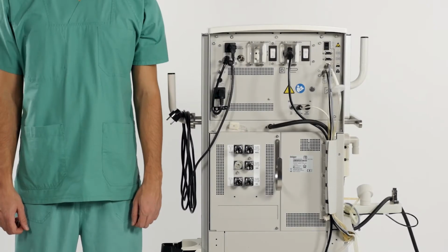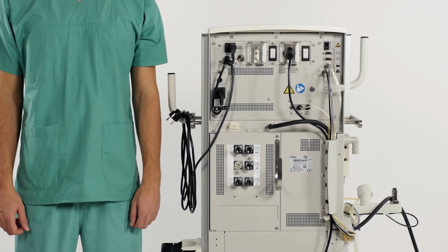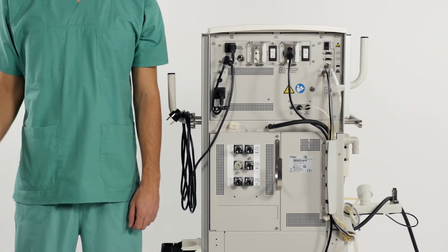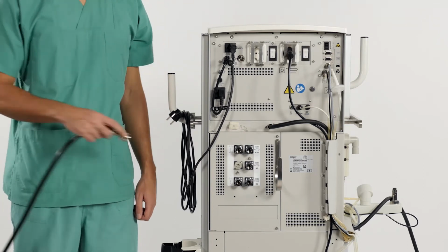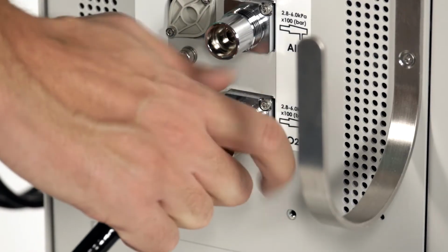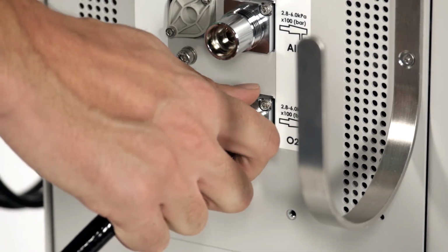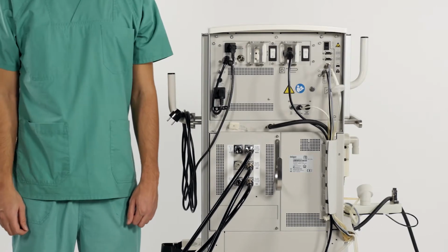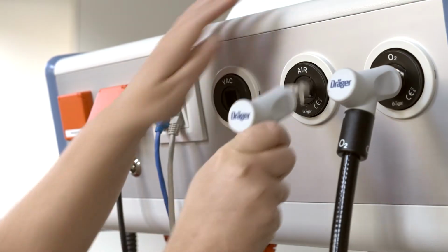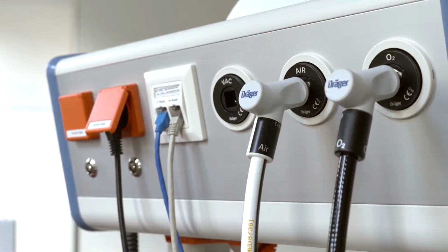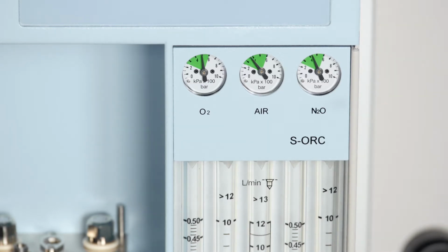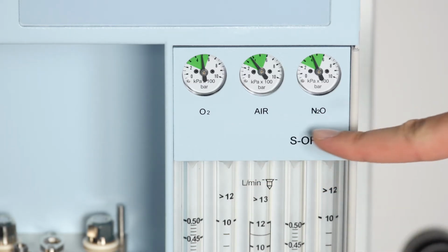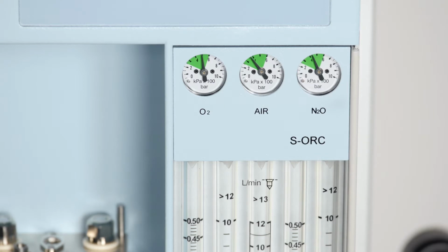In this chapter, we would like to show you how to set up the Fabius. First, we check the supply connections. Connect the pipeline hoses for oxygen, nitrous oxide and medical air to the outlets on the rear side of the machine. Plug the hoses into the relevant outlets in the wall. Check gas line pressures on the gauges located on the front of the Fabius. The indicator should be within the green zone.